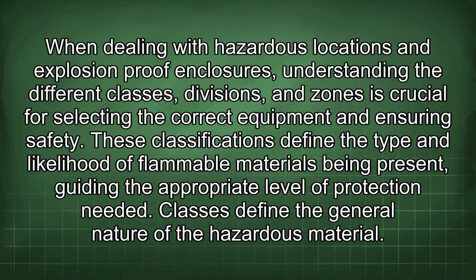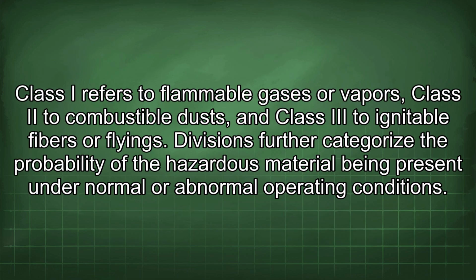When dealing with hazardous locations and explosion-proof enclosures, understanding the different classes, divisions, and zones is crucial for selecting the correct equipment and ensuring safety. These classifications define the type and likelihood of flammable materials being present, guiding the appropriate level of protection needed. Classes define the general nature of the hazardous material. Class I refers to flammable gases or vapors, Class II to combustible dusts, and Class III to ignitable fibers or flyings.